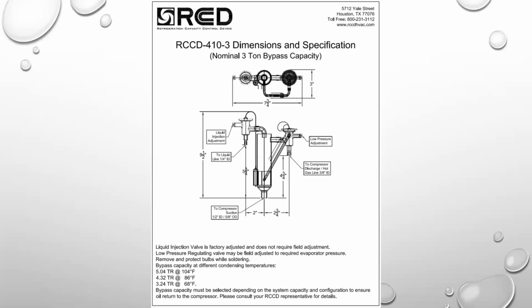That suction connection down there is a 1/2 inch ID or 5/8 OD. The reason it's set up like that is if you want to put a 5/8 ball valve on there, you just slide it over it. Or if you need to go a little bit of a distance, you can put 1/2 inch line in there. It just makes it easier. It gives you some advantages.